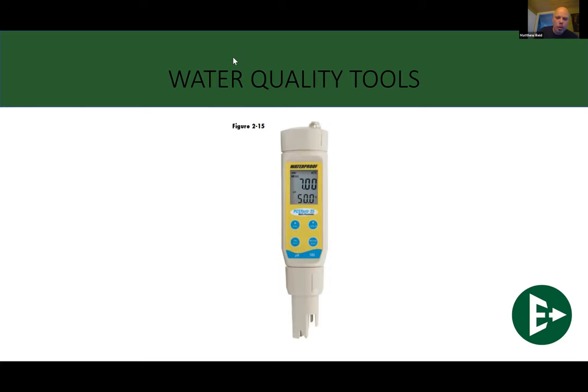One question popped through. Is distilled water right to fill a system with? Distilled water is not terrible to fill a system with. The only thing that I would say is, again, when you get down to that just complete basic H2O, you do create a bit of hungry water. So if you do that, you must put in a chemical additive, something like a stabilizer or oxygen scavengers, some sort of stabilizer to make sure that it's not creating that hungry water where it's going to be pulling ions from wherever it possibly can.